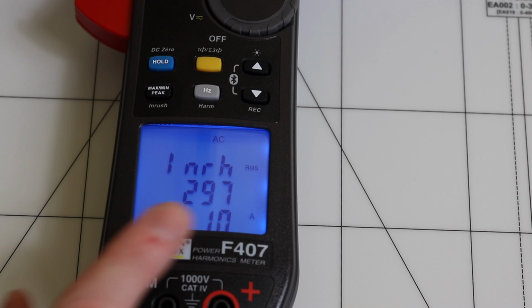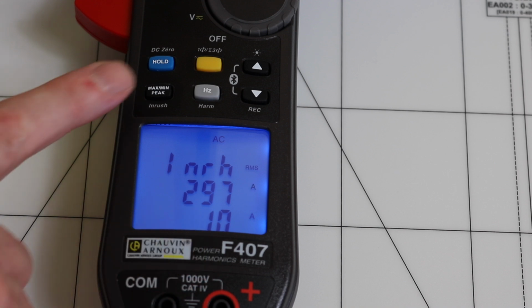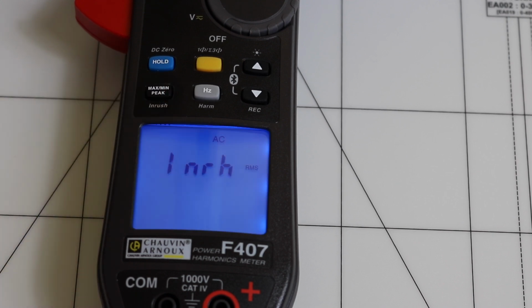What I'm just going to do is show you this trigger level and the way it changes. I'm going to turn the test set on first and give a 1 amp injection, which this will see as 50 amps, and with my 50% setting that should then go to a trigger level of 75 amps. So let's switch the test set on. There's inrush, it's detecting the current. You see we've got 74 amps trigger level now, and then it will step up. It's picked up 297 amps inrush on this occasion. So that's the functionality there.